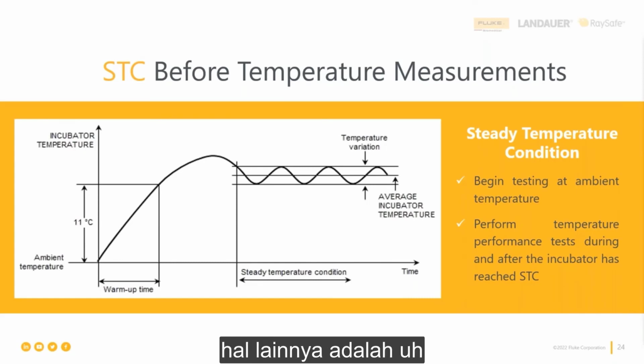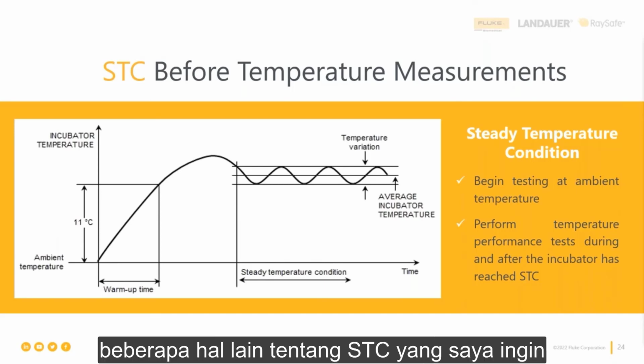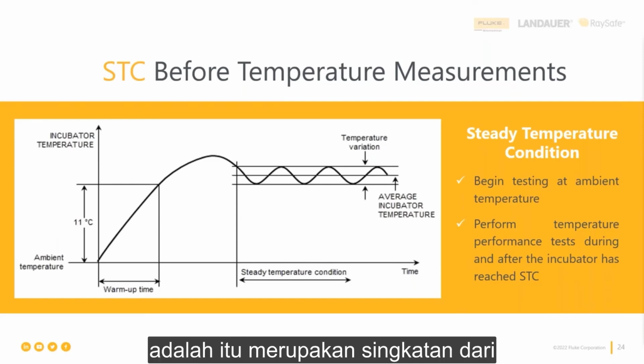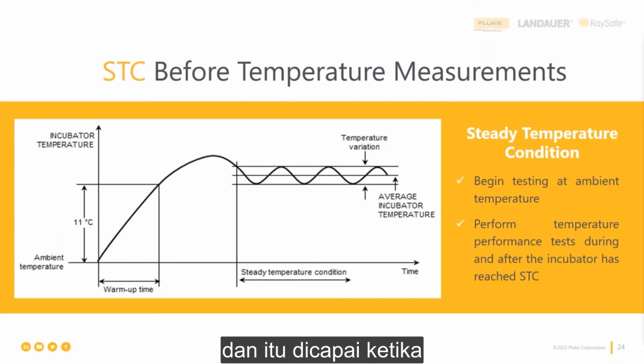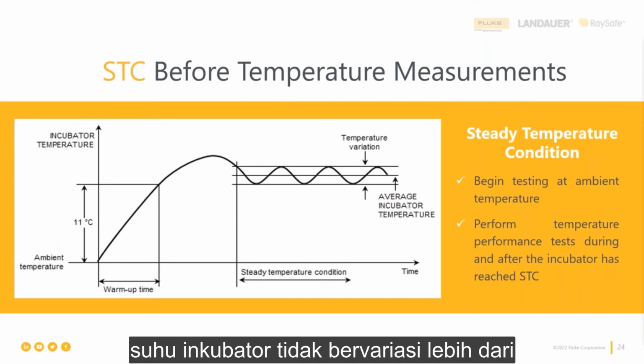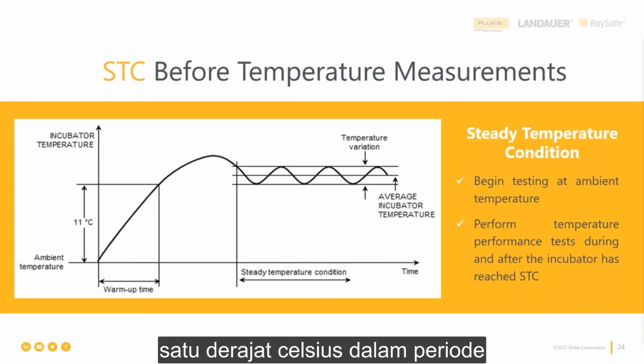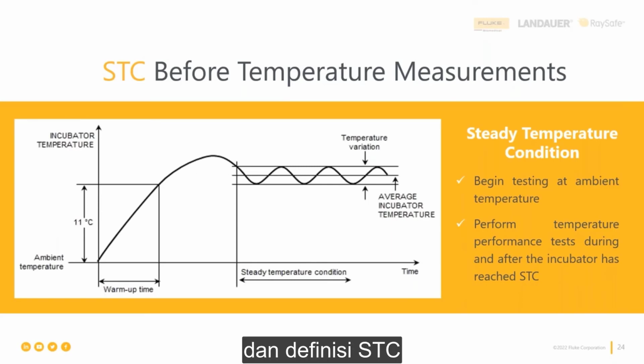The other thing is the temperature overshoot, right? That should be no more than 2 degrees Celsius above the set point. Some other things about STC that I want you to remember is that, one, it stands for steady temperature condition. And it's achieved when the incubator temperature does not vary by more than 1 degree Celsius over the period of 1 hour. So that's the definition of STC. So again, just remember those: the warm-up time, the overshoot, and the definition of STC.